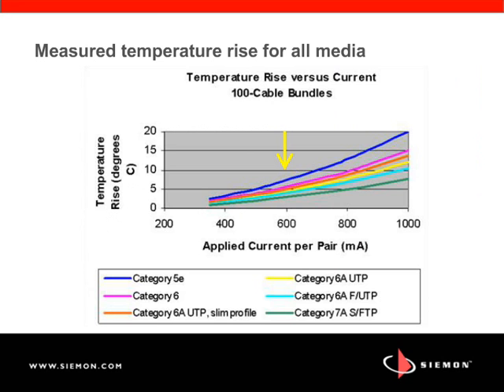Well, this is a chart that was developed to demonstrate what happens when the 600 milliamp current associated with the PoE type 2 application, or the PoE Plus application, is applied to 100 cable bundles of different grades of cabling. What we see here at the arrow is that current associated with type 2 PoE, and I'll share some numbers with you. The temperature rise within a category 5E bundle is 7.2 degrees Celsius. And category 5E is the minimum grade of cabling recognized for support of the PoE type 2 application.